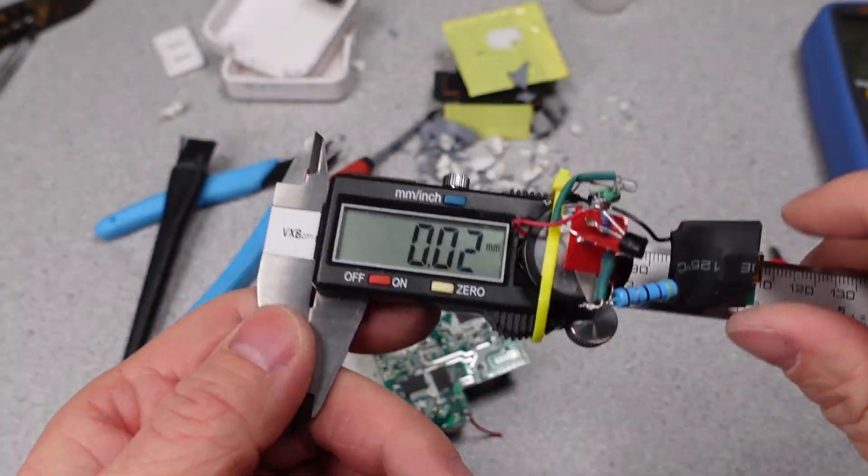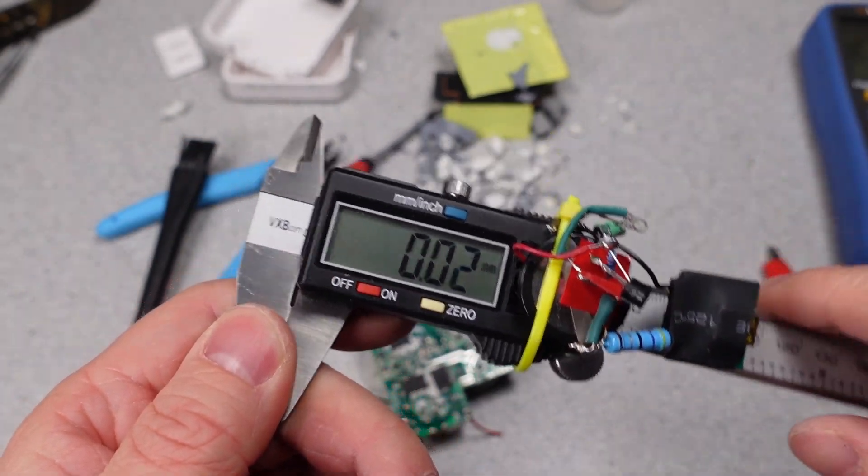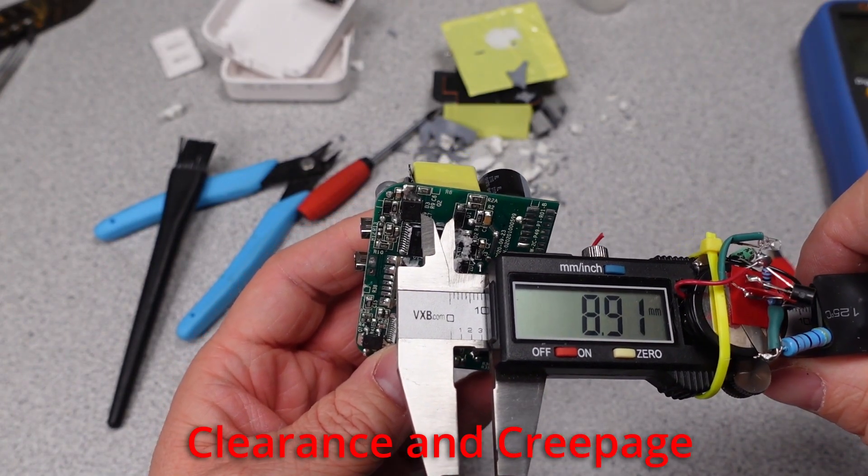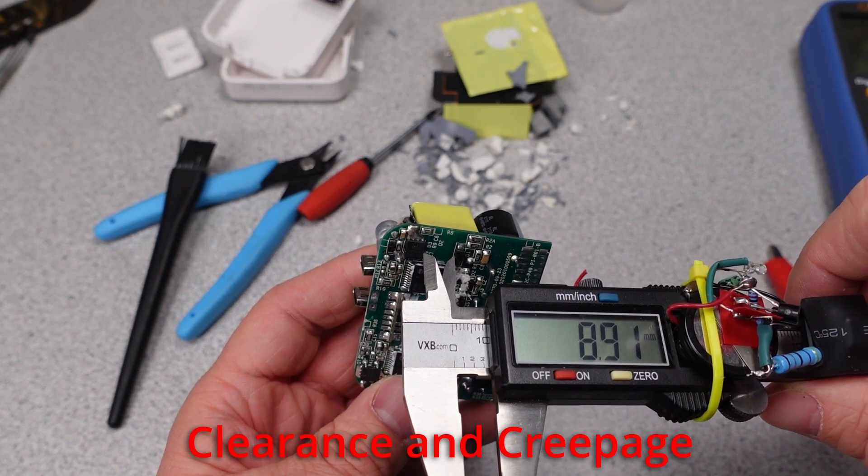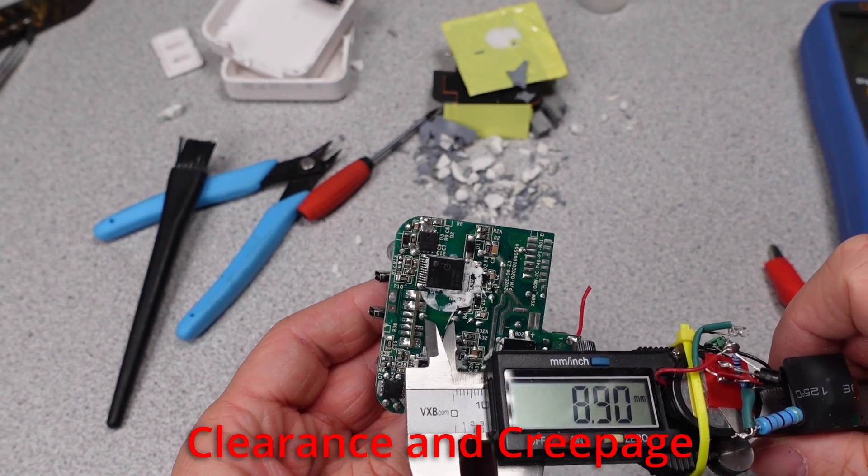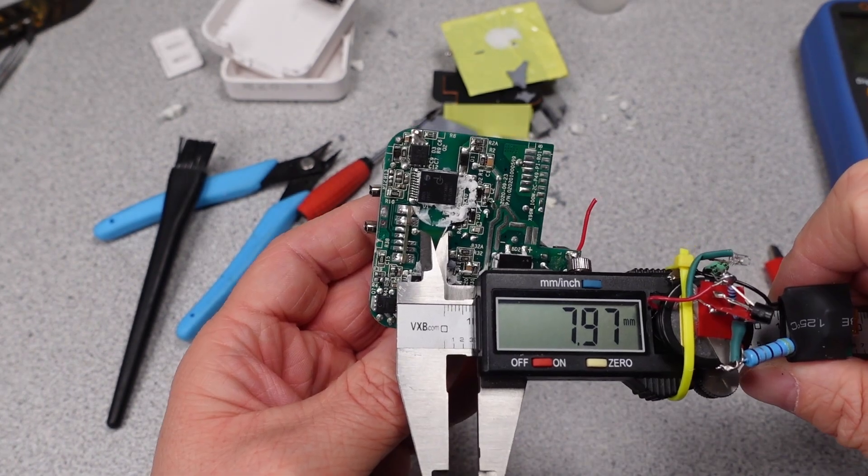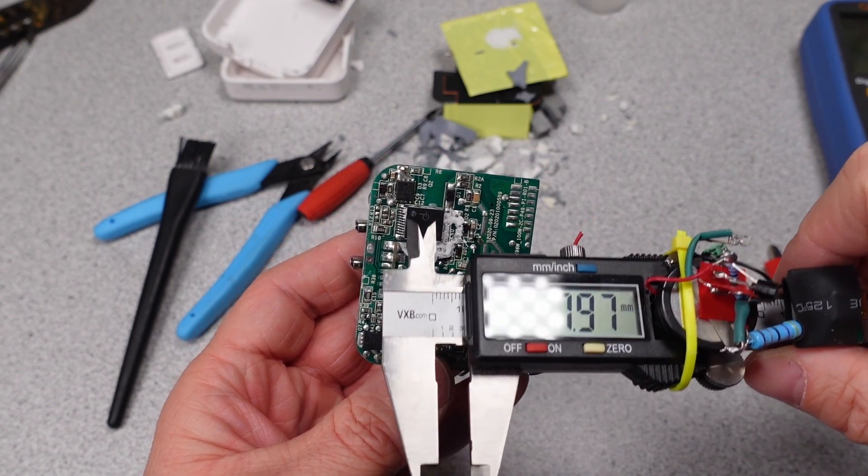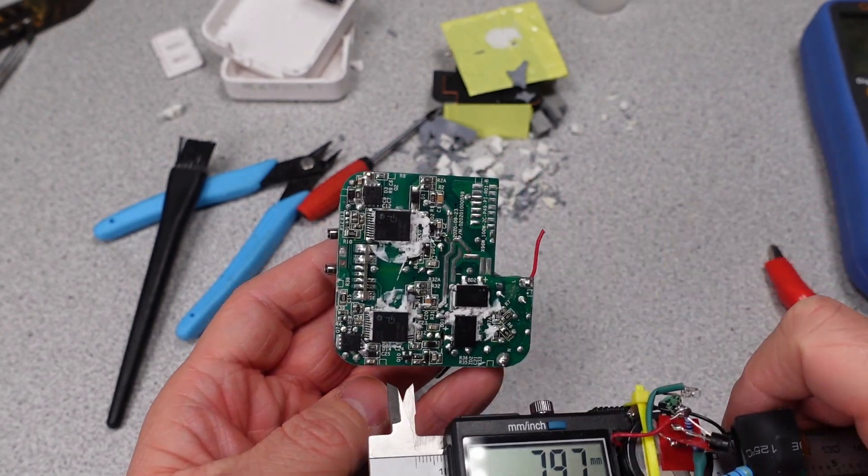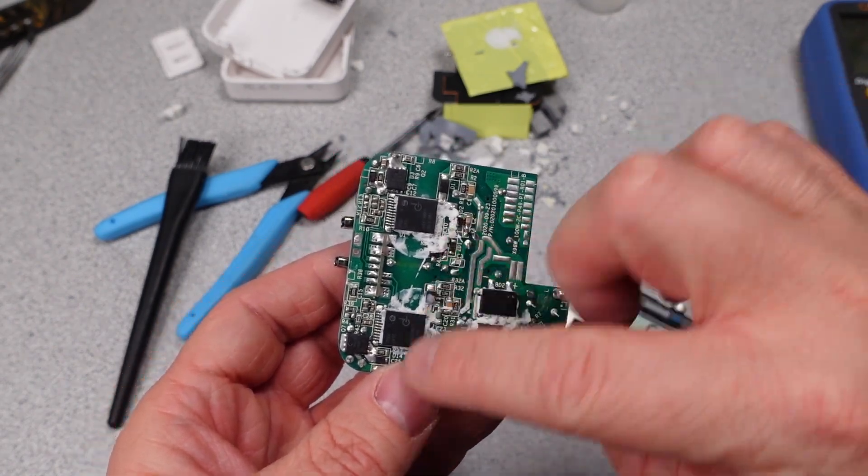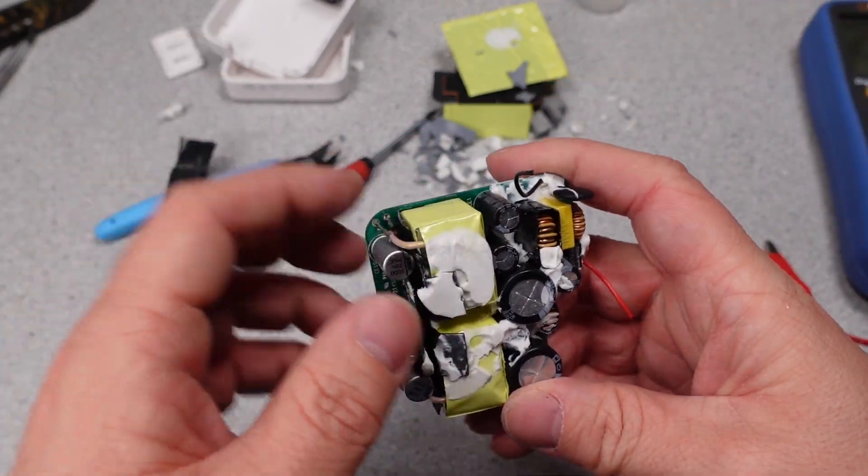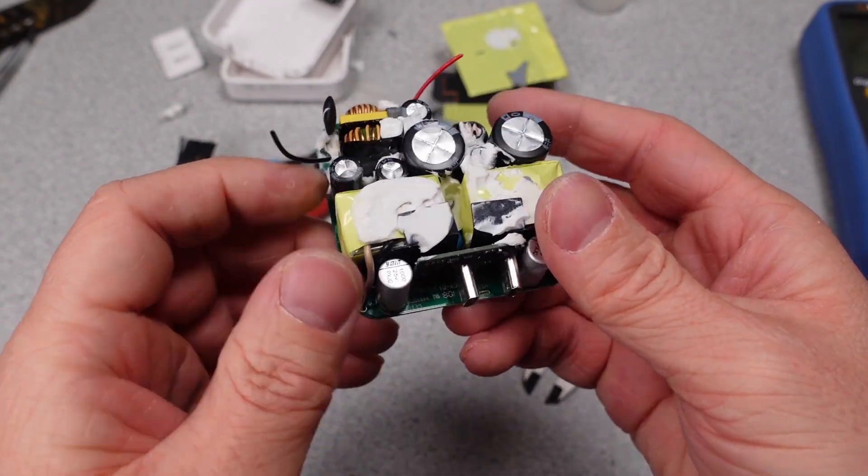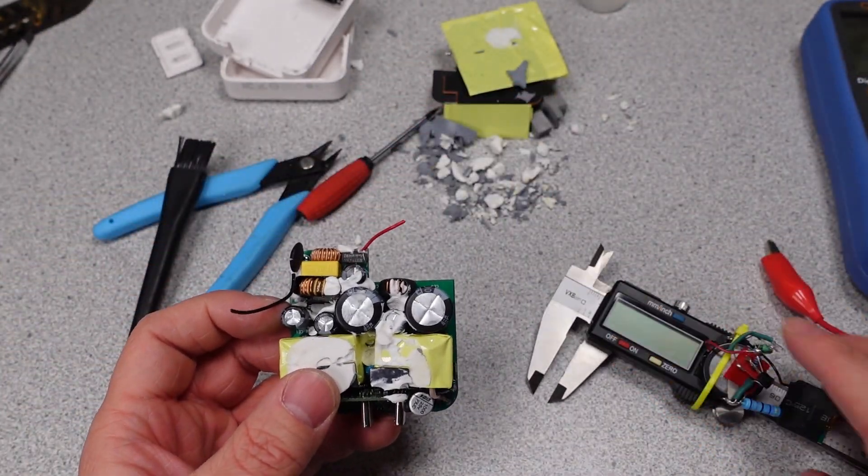I really need to do the video on how I modified these calipers. All right, so there we can see we've got about 8.9 millimeters clearance between these components. That's acceptable. Here's the same distance with our suppression capacitor. Still talking about 8 millimeters with the suppression capacitor, so no problems there. So it's definitely got the separation between the two sides of the boards. So they're meeting the requirements, at least on this side of the board, but I think we're going to pop these transformers off the board and explore a little more to get the full picture with this one.